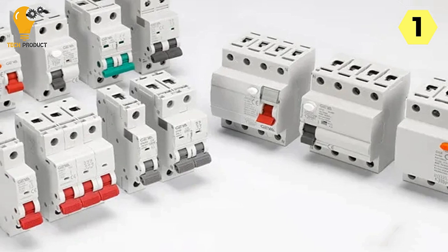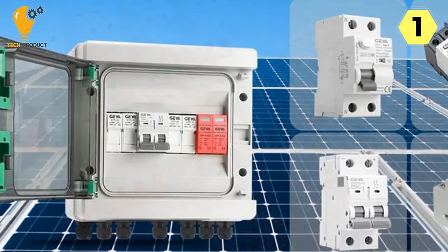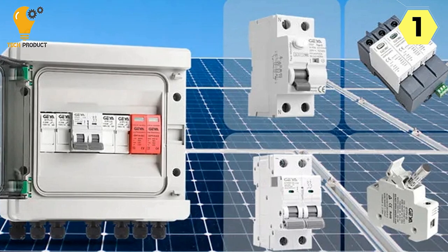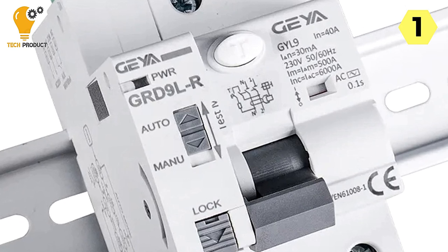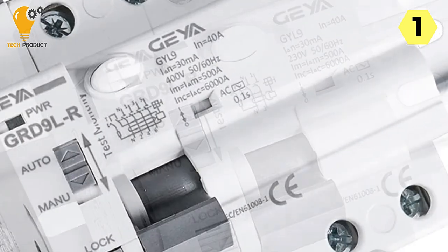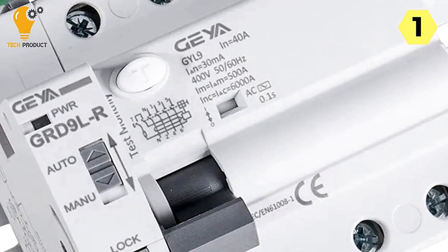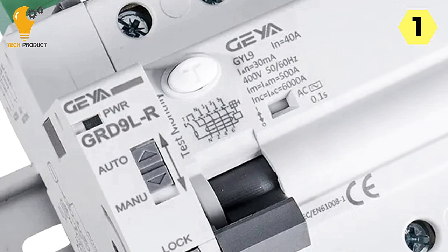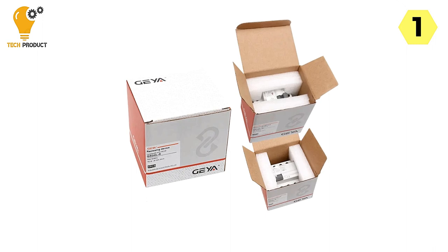In the event of an electric trip, this circuit breaker automatically switches on the distribution board, addressing issues promptly to minimize disruptions. The auto-reclosing interval time can be customized, with options ranging from 10 seconds to 300 seconds, allowing you to fine-tune your power management strategy. The circuit breaker also includes built-in reclosing times, with an alarm feature that activates through an auxiliary contact if continuous closing failures occur within 15 minutes.